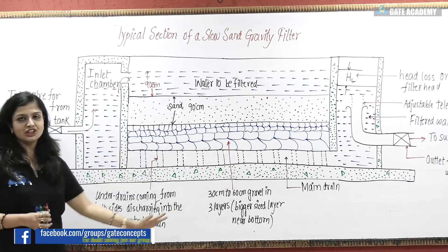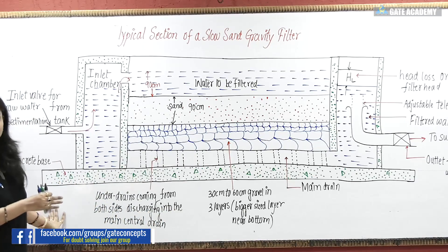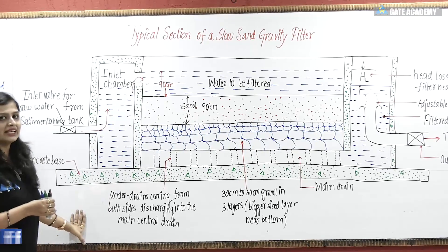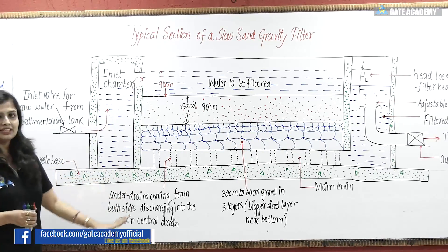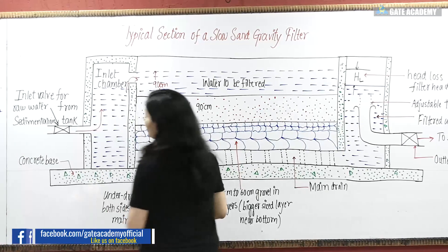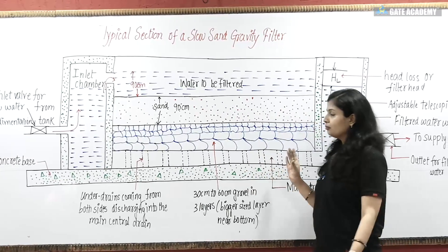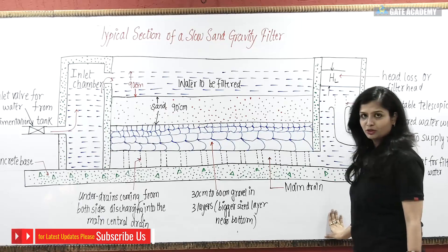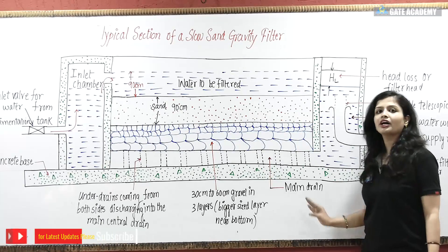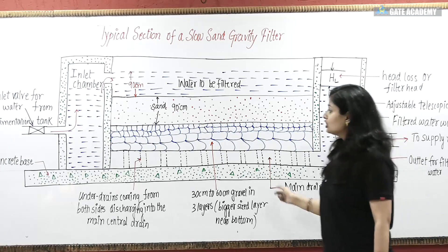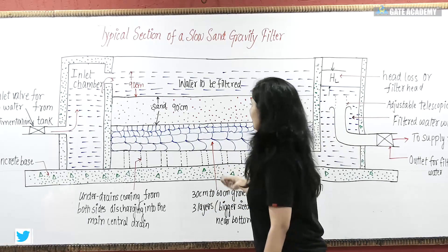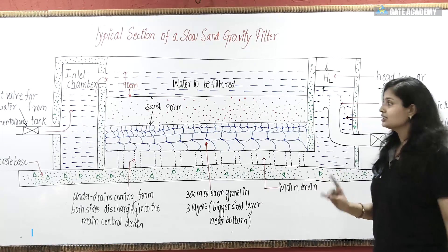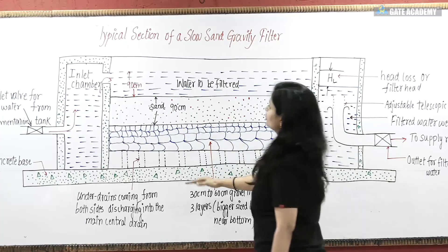Here is the typical section of a slow sand gravity filter. Take a first look at this picture so that you will get a clear view of the slow sand gravity filter. We will discuss various construction details of slow sand gravity filters. First, you can see this is a rectangular tank which we call the enclosure tank. The depth is around 2.5 to 3.5 meters and its area is 100 to 2000 meters square.